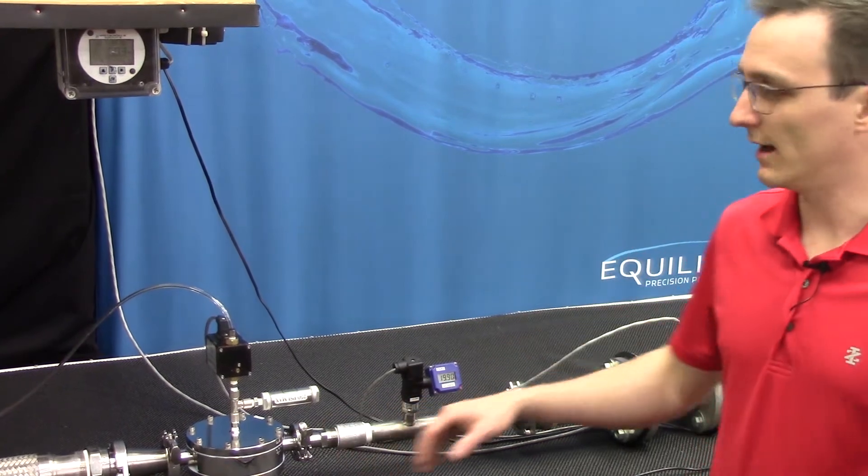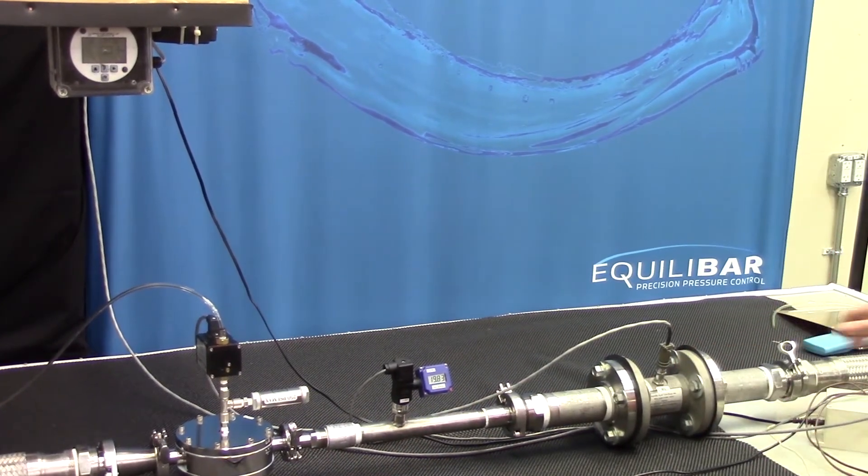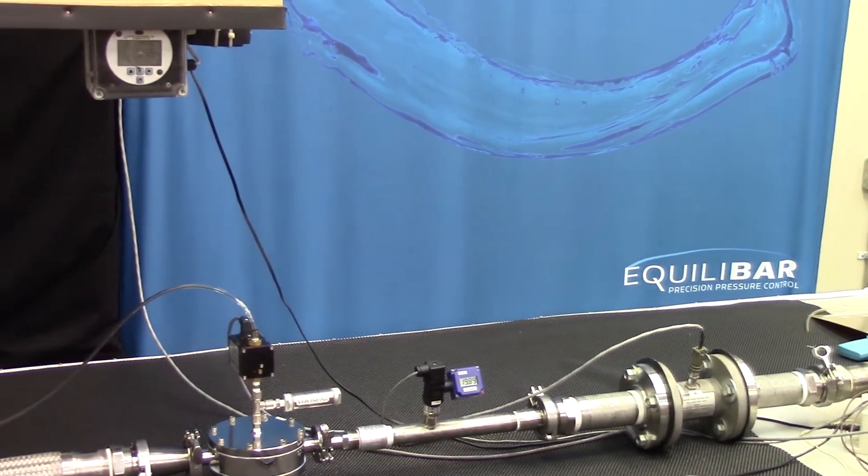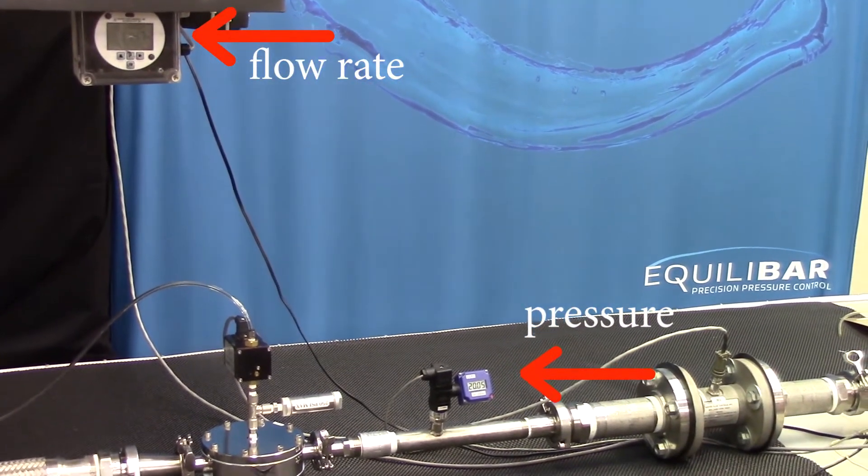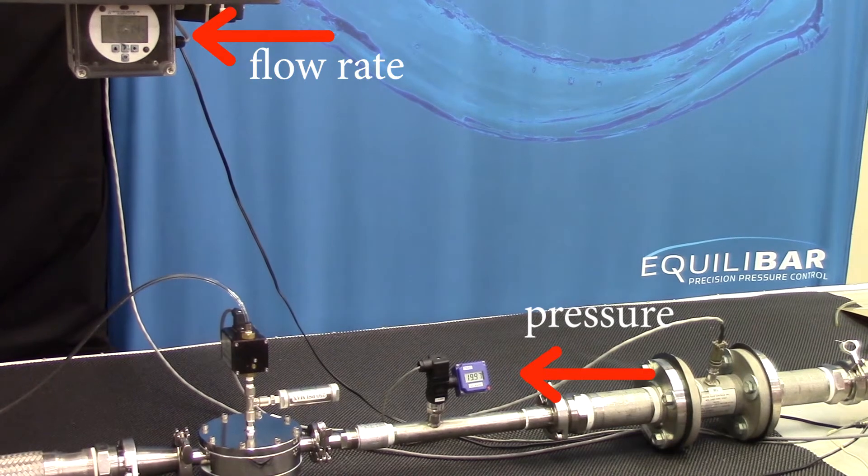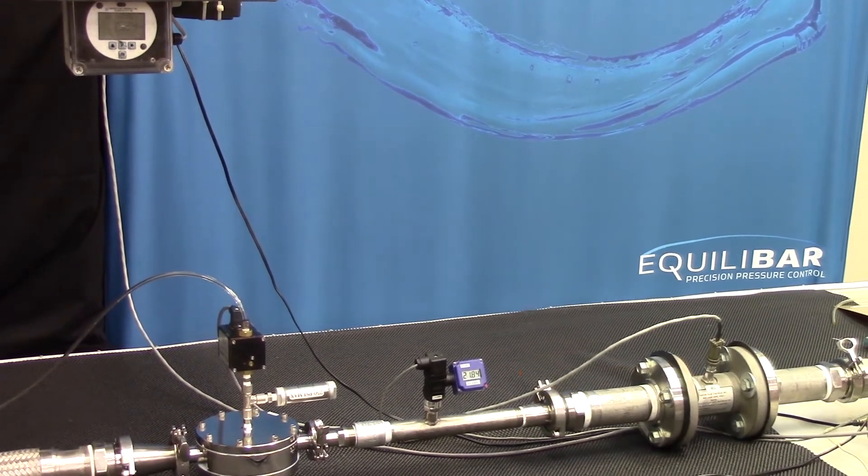All right, so now we're going to begin. We are not plotting this flow in LabView, but we're going to present it on this screen here, and we're going to increase it to 30 gallons per minute, which will saturate the valve we're testing.